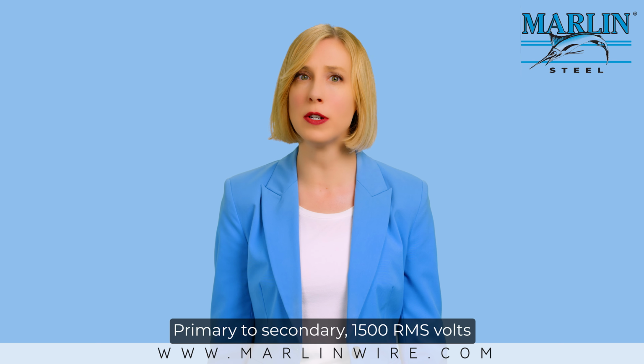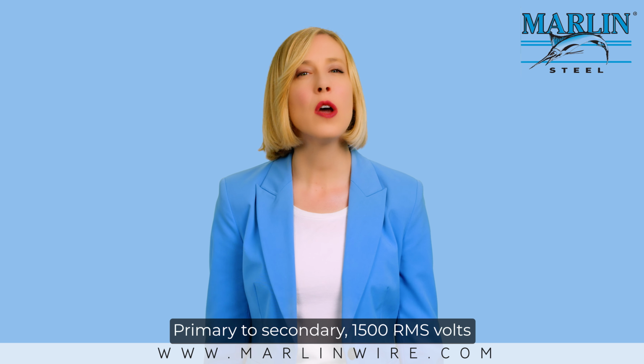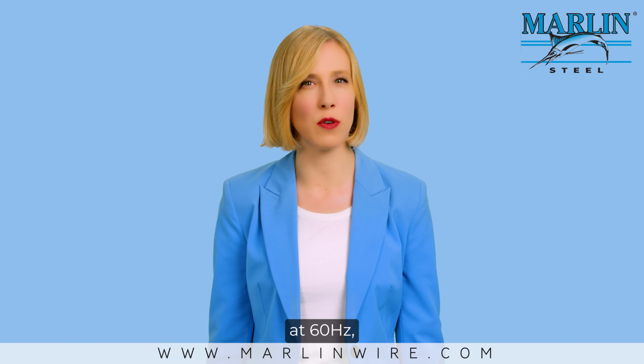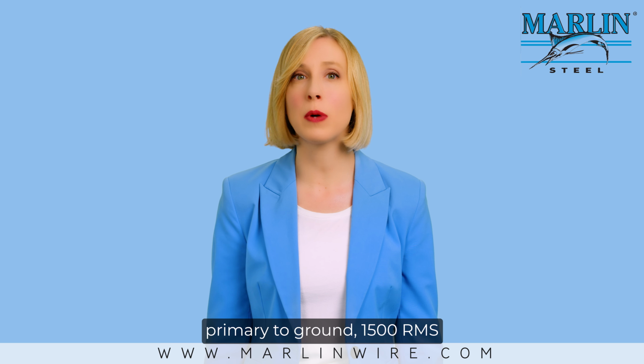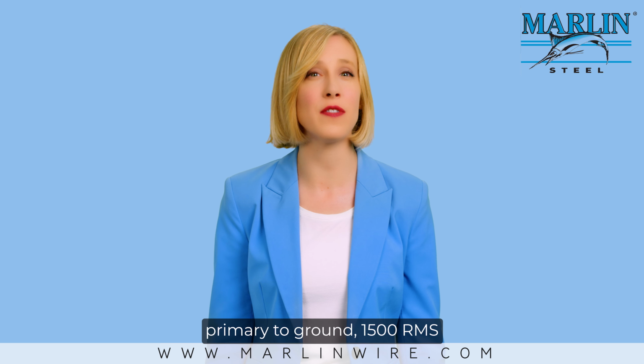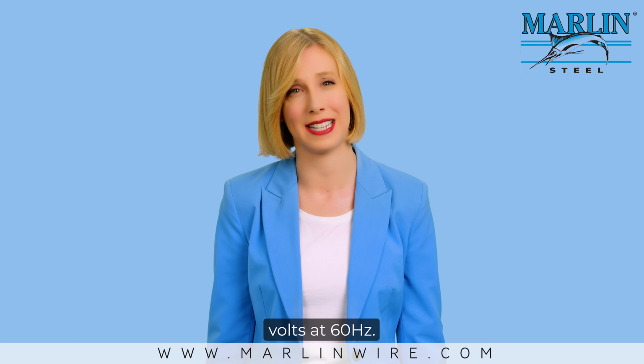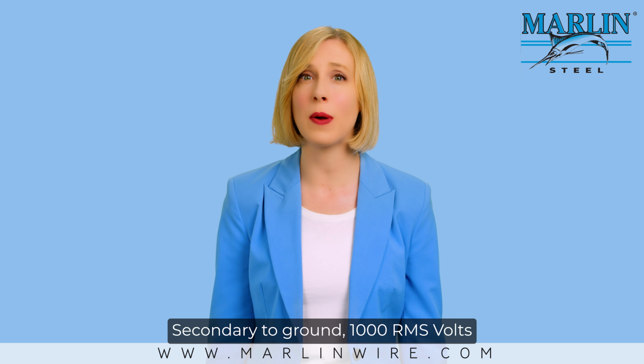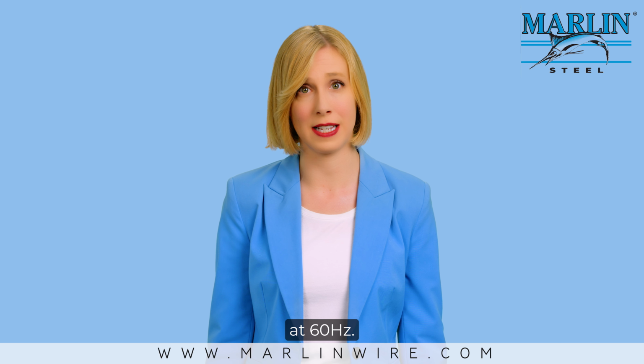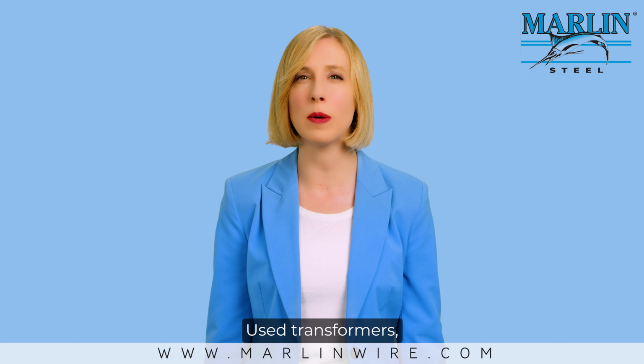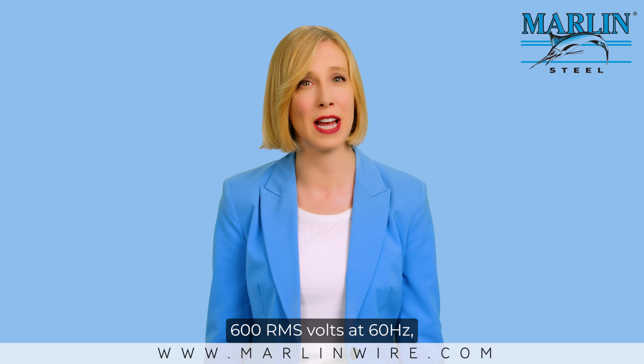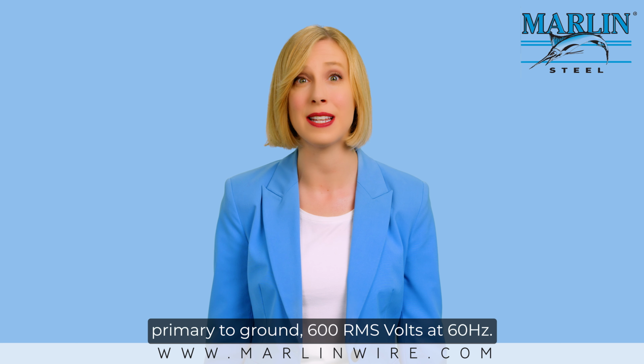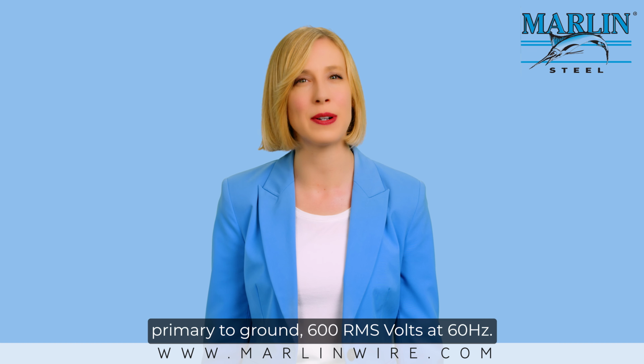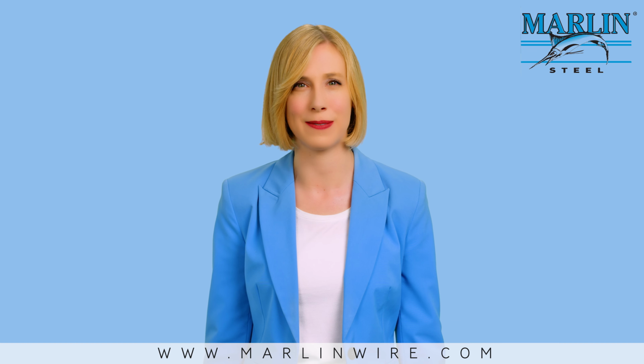New transformers, primary to secondary, 1,500 RMS volts at 60 Hz. Primary to ground, 1,500 RMS volts at 60 Hz. Secondary to ground, 1,000 RMS volts at 60 Hz. Used transformers, primary to secondary, 600 RMS volts at 60 Hz. Primary to ground, 600 RMS volts at 60 Hz.